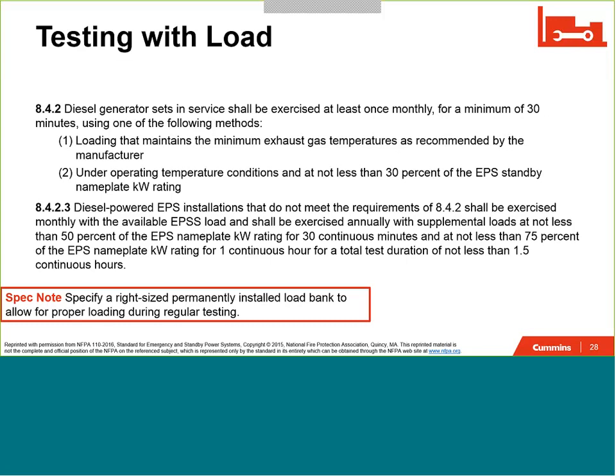So NFPA 110 offers another recommendation, that it can be operated at not less than 30% of the standby nameplate rating. And that's typically what we see most often done. So this is once a month, 30 minutes, 30% load. NFPA 110 goes on to say, if that is not able to be done, here are some other recommendations. It says if you can't do that, it shall be exercised annually, once a year, at not less than 50% for 30 minutes, and at not less than 75% for 1 continuous hour.